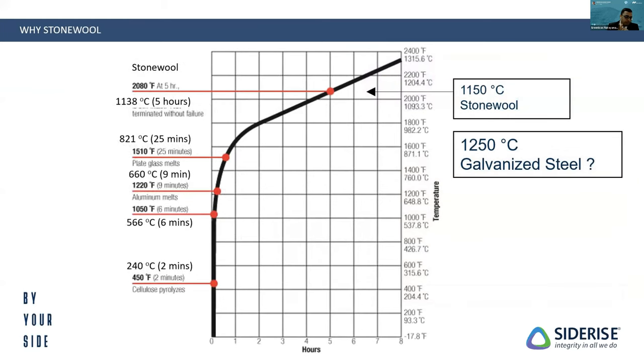Another important point: various test standards use the same time-temperature curve. The resistance or time-temperature curve that stonewool must perform at is very high temperature. We often use a galvanized tray and say it can stop smoke or fire, but when put into testing, the metal will get hot and transfer heat immediately. Ideally, steel cannot be a good fire resistance product because it resists fire but not heat. With heat, it becomes flexible and may lose its characteristics.